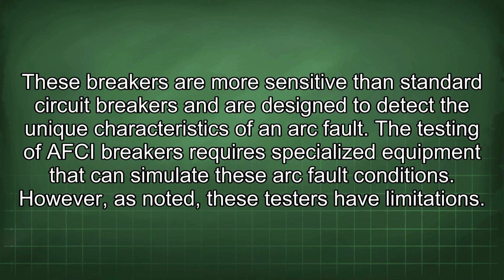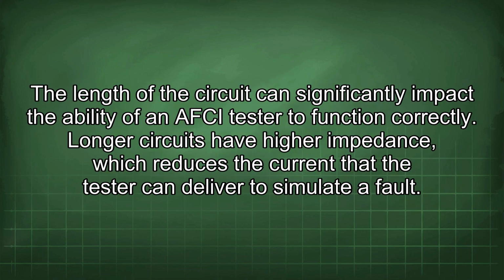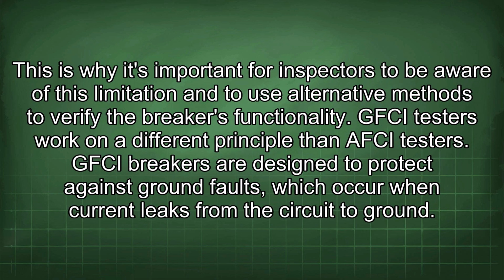However, as noted, these testers have limitations. The length of the circuit can significantly impact the ability of an AFCI tester to function correctly. Longer circuits have higher impedance, which reduces the current that the tester can deliver to simulate a fault. This is why it's important for inspectors to be aware of this limitation and to use alternative methods to verify the breaker's functionality.